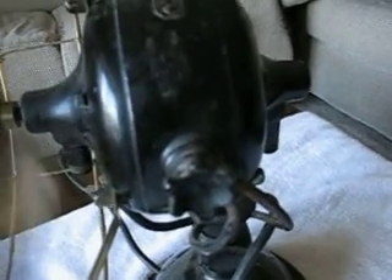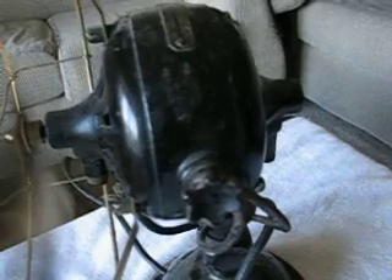Three-speed stationary. The centrifugal switch is very quiet. Let's crank them up on high first. There, as soon as the motor got quiet, that was the switch opening.